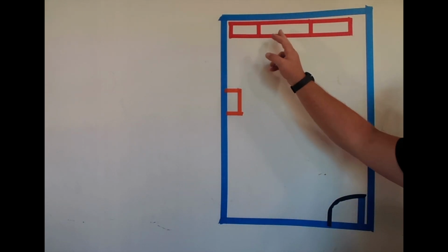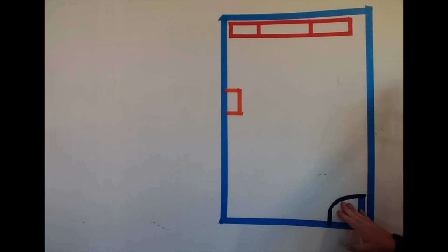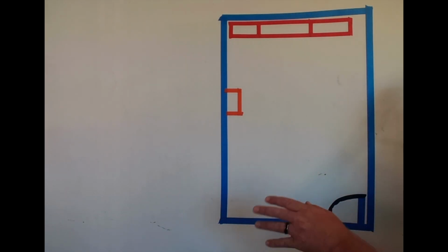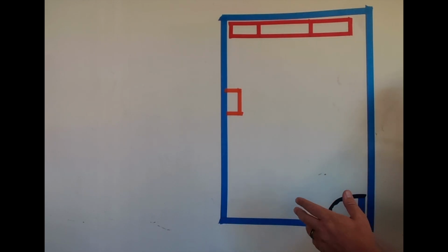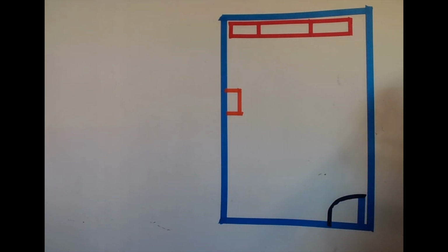We've got 3 racks of batteries. We've got 1 HVAC in the room, and we have 1 entrance/exit into the space. So we'll also go over the design while we're doing this. So what we're going to do is we're going to mount over here on this space. We are going to mount the Gen 3 system with the hub, and then we're going to build it out from there. We'll route the cables as nicely as we can, but at the same time, what we're going to try to do is give you the ability to install the system, plus give you a general outline for a basic basis of design.